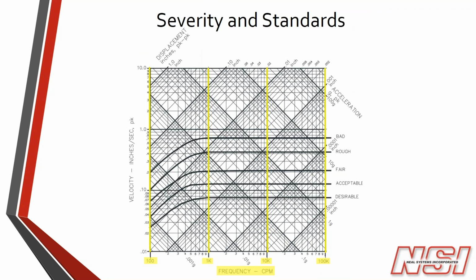So looking at this chart, I'm going to highlight some of the different axes because it's pretty complicated when you first look at these things. Frequency is the x-axis, and so you'll see the frequency increases from 100 CPM, that's cycles per minute again, up to 100,000 cycles per minute. And these are logarithmically scaled intervals here. So 100, 1,000, 10,000, 100,000. And so that's kind of how this chart works.